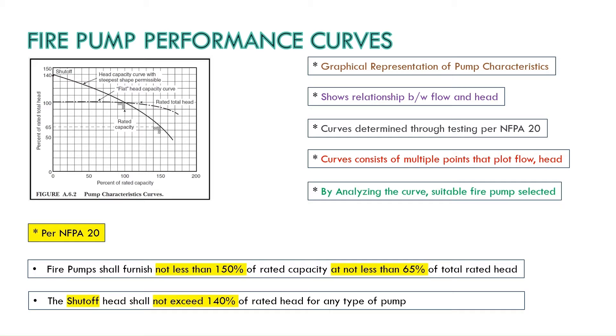I will explain you this one by just considering one small fire pump. Here we have 1000 GPM fire pump at 100 PSI. This is the rated capacity and 100 PSI is the total rated head. Now this pump shall produce 150% of the rated capacity at or at least 65% of total rated head. So in our case when we have 1000 GPM at 100 PSI then 150% of 1000 will be 1500 GPM and we need to get at least 65% of this 100 PSI. So it will be about 65 PSI.